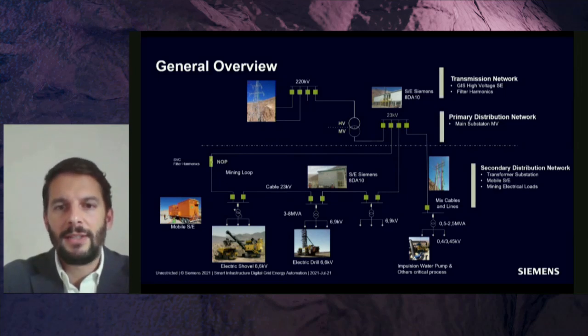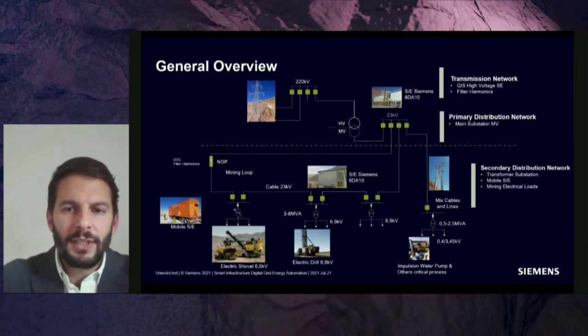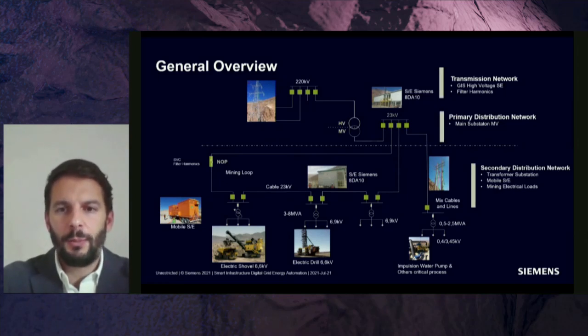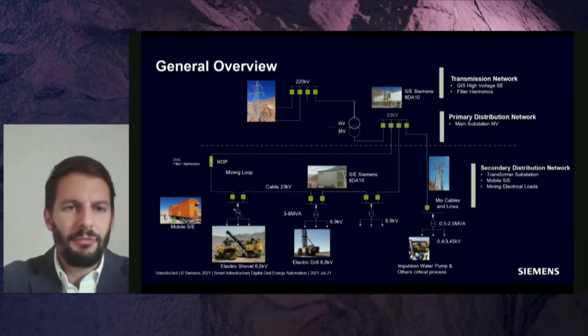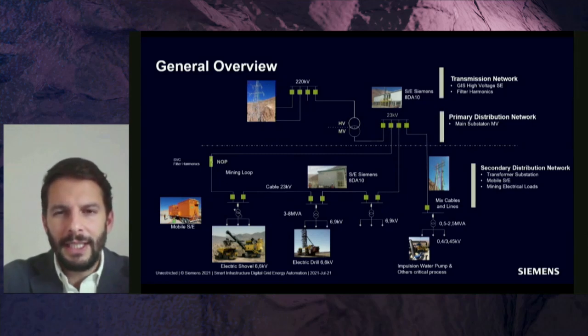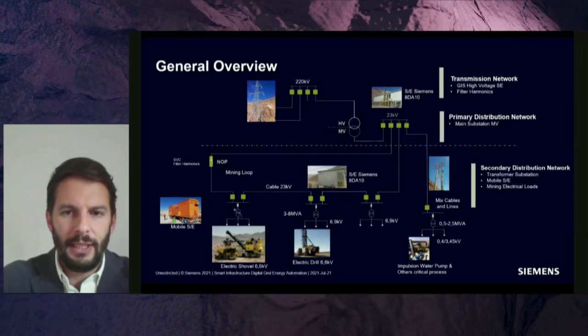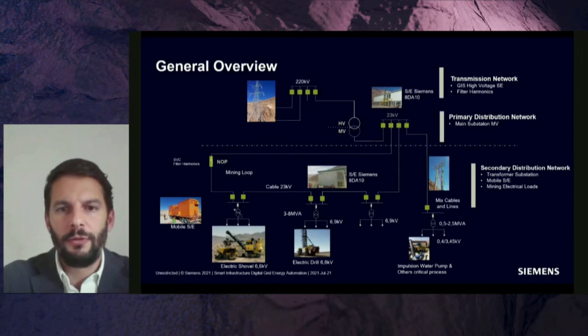I would say with such an approach, we are supporting the redundant supply of loads and also allowing full flexibility to connect and disconnect loads, for example, in the case of maintenance works. But I would say that's just one part of the answer. Looking at the technology available today, namely the grid edge automation, what is interesting is what can be implemented on the loop as part of the so-called high-speed self-healing algorithms and grid reconfiguration without any intervention of the network or system operator. Let's look into the working principles of such technology.